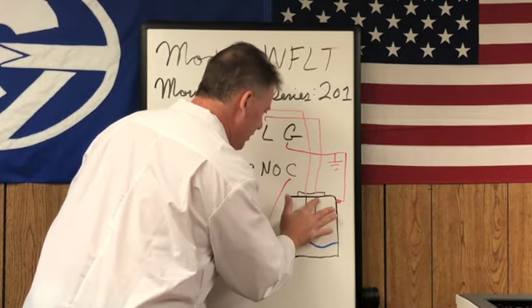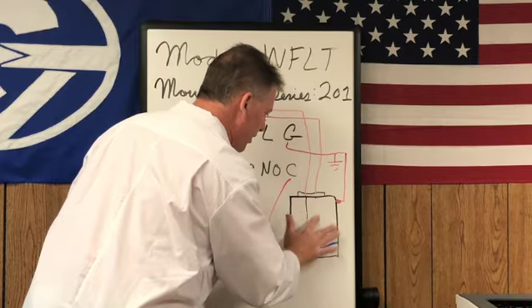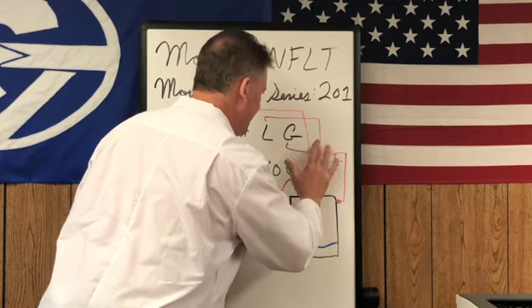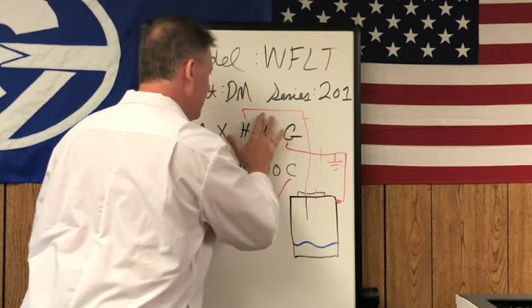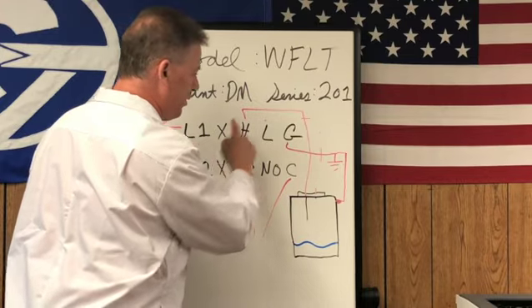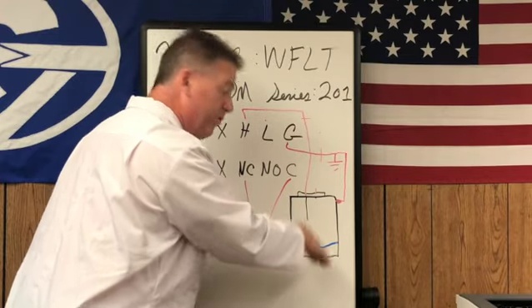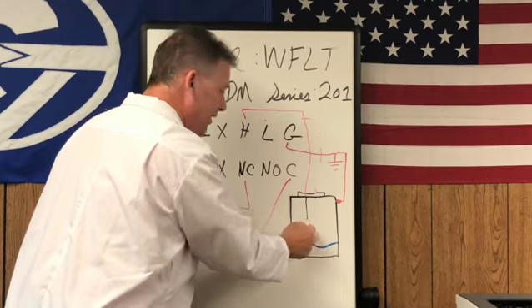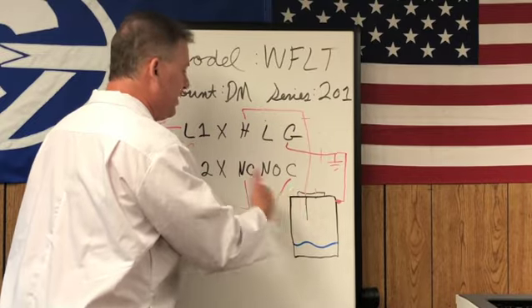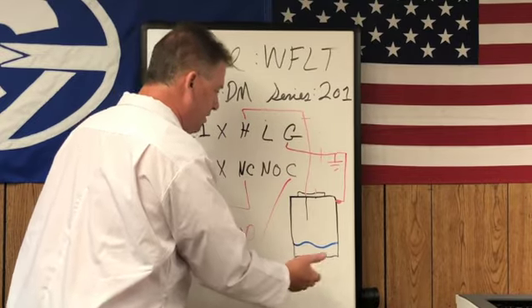You're not going to use the ground at all. You're not going to use the low terminal at all for this. We're just going to take that completely off. You're just going to use the high terminal to bring to the probe whatever level it is in the tank. And that's going to give you your on-off switch. Liquid touches it, relay energizes. It drops off, relay de-energizes.